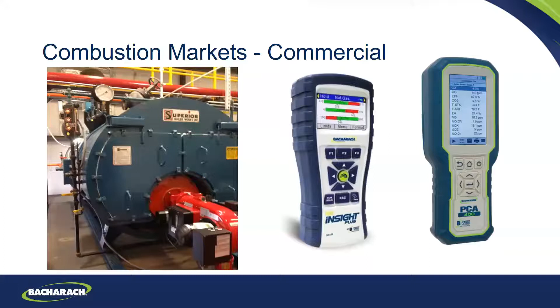And if you really want to read high CO, like maybe you have engines, this would be the unit to use because it can go up to 40,000 parts per million. If that's not enough, there's a higher range sensor that can go up to 80,000 parts per million, way more than enough. Some engine manufacturers, like if you're working on a Caterpillar or Waukesha engine, that would be the unit you want, as well as for bigger boilers, like these 25 million BTU boilers, you should definitely be using the PCA 400.